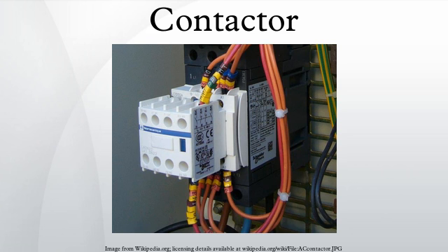Modern medium-voltage AC motor controllers use vacuum contactors. High-voltage AC contactors may use vacuum or an inert gas around the contacts. High-voltage DC contactors still rely on air within specially designed arc chutes to break the arc energy. High-voltage electric locomotives may be isolated from their overhead supply by roof-mounted circuit breakers actuated by compressed air. The same air supply may be used to blow out any arc that forms.